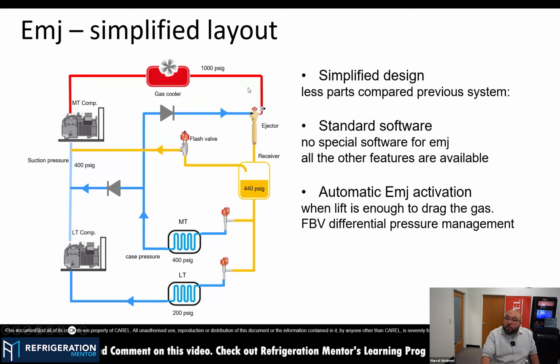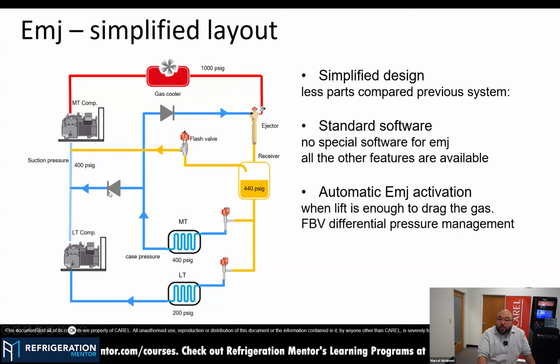As I mentioned, the main function of the ejector is working as a high pressure valve. So in all conditions, the ejector will be controlled. The logic residing in the PRAC or in the ejector manager prioritizes control of the gas cooler pressure, so we are making the expansion. Here you can see that for my MT cabinets, or MT cases, the line is split into two pipes. One goes to the MT suction, combining with the LT line, and the other comes from the MT cases and goes to the ejectors. We have two new components here, two check valves. And why do we have these check valves here? Because of the effect of the ejector.